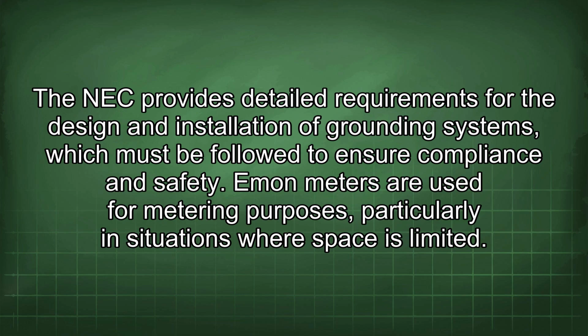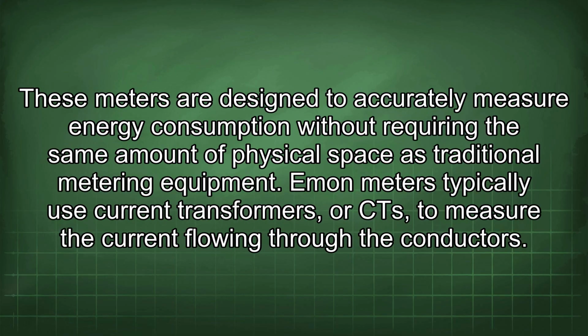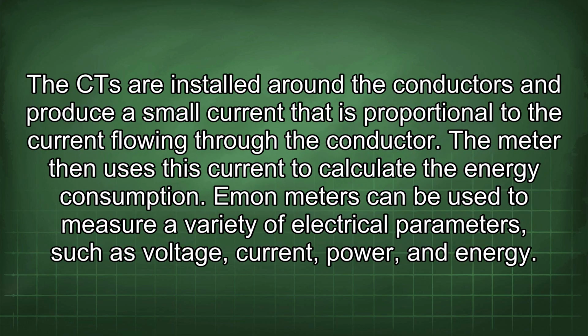and safety. Emon meters are used for metering purposes, particularly in situations where space is limited. These meters are designed to accurately measure energy consumption without requiring the same amount of physical space as traditional metering equipment. Emon meters typically use current transformers, or CTs, to measure the current flowing through the conductors. The CTs are installed around the conductors and produce a small current that is proportional to the current flowing through the conductor. The meter then uses this current to calculate the energy consumption.